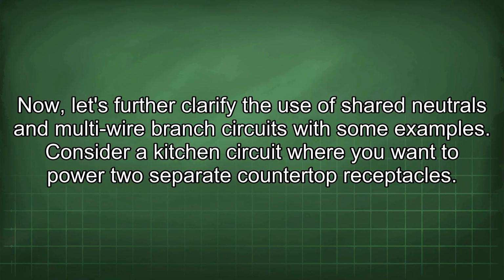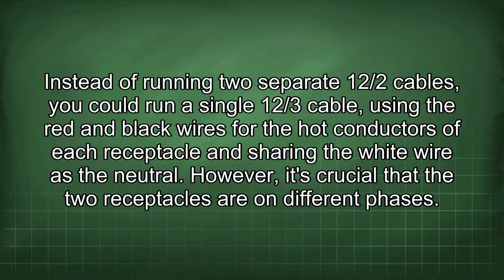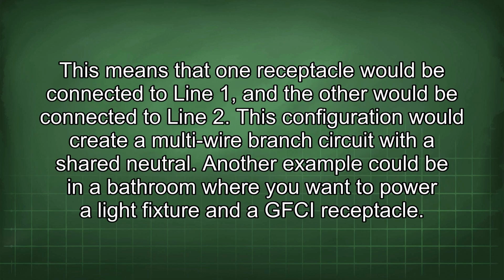Now, let's further clarify the use of shared neutrals and multi-wire branch circuits with some examples. Consider a kitchen circuit where you want to power 2 separate countertop receptacles. Instead of running 2 separate 12/2 cables, you could run a single 12/3 cable, using the red and black wires for the hot conductors of each receptacle and sharing the white wire as the neutral. However, it's crucial that the 2 receptacles are on different phases. This means that one receptacle would be connected to line 1 and the other would be connected to line 2. This configuration would create a multi-wire branch circuit with a shared neutral.